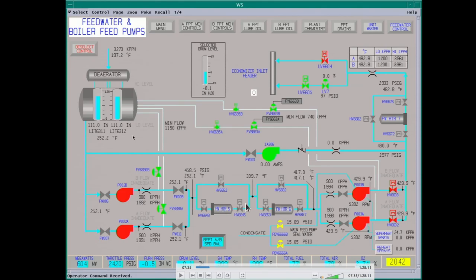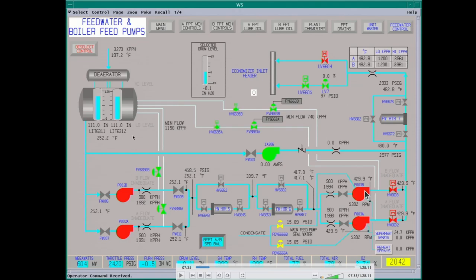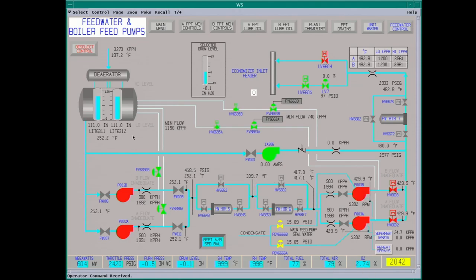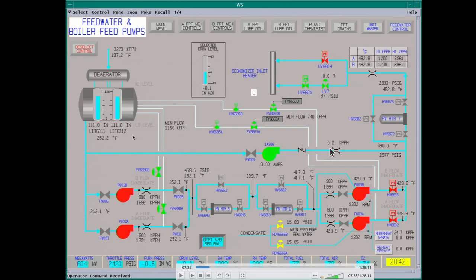Your flow path is to your booster pumps, then feed water heater 5, feed water heater 6 — the water is heated up quite a bit to increase efficiency. It comes into your main feed pump, then goes up to feed water heater 7, then to the boiler. There are no level control valves on this system — it's run off of the RPM of the feed pumps. It uses sealing water for sealing the main feed pump. This is the startup feed pump — it's an electric pump used when there's no steam to get the plant running. When running this, you use a level control valve; it runs 3-element control at about 1,400 PSI.